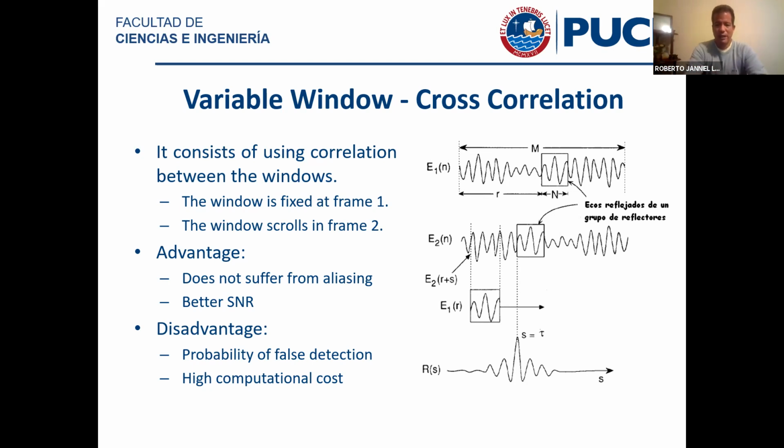And the other issue was that it had a very high computational cost. You have to understand that the challenge always, especially for ultrasound, is to create images in real time. So this was an algorithm that was way more expensive than Kasai's algorithm from a computational point of view. And that would have been okay had there been real advantages, but it would still give you images that would suffer from distortions. And actually these distortions could be even worse than the ones provided by Kasai's algorithm.